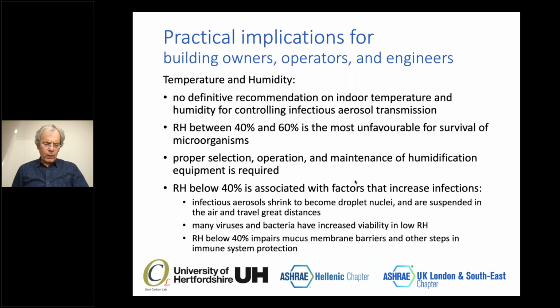Temperature and humidity are important parameters, and whereas ASHRAE makes no definite recommendation on indoor air temperature and humidity for controlling infectious aerosol transmission, it is known that relative humidity between 40% and 60% is most unfavorable for survival of microorganisms. This is also a very favorable relative humidity for humans. So we need to keep relative humidity within these boundaries, and that can be achieved by proper selection, operation, and maintenance of humidification equipment in HVAC systems.